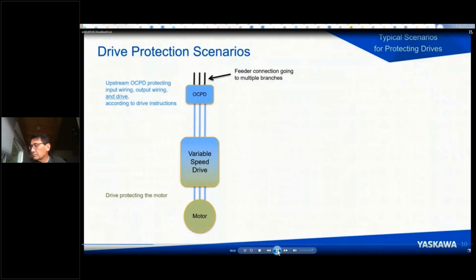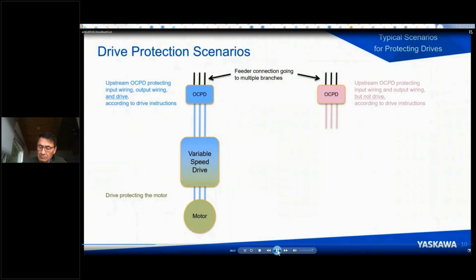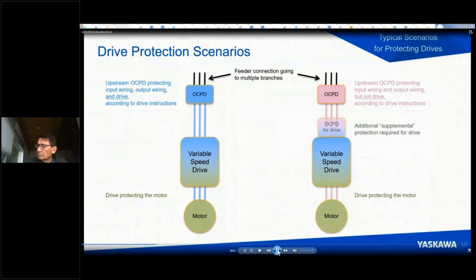You know this by looking at the drive instructions and making sure that what's upstream is actually listed in the instructions for the drive. If it's not listed as a UL protected device, then you have this other scenario, where your overcurrent protective device is protecting the conductors, but then you have to add an additional supplemental device in order to completely protect the drive. In some cases that might be a breaker, but often when you have to add something, it's going to be fuses. So these are two protection scenarios you can get into.